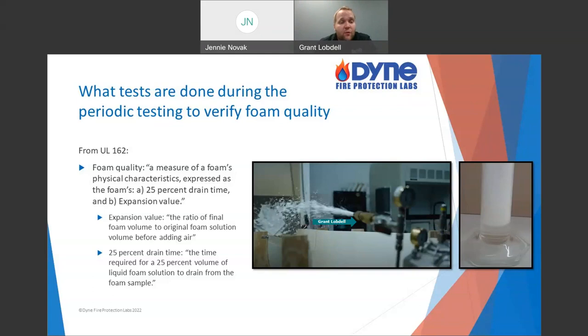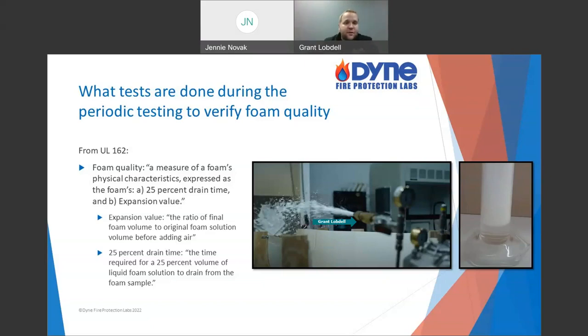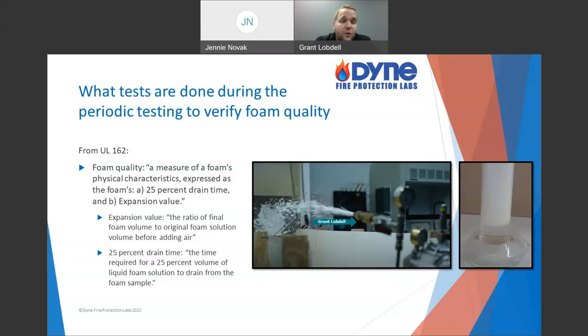Expansion ratio is very important with foam. We have Class B fires, liquid fires. If I were to just spray water on one, it's going to splash everywhere. Also, water is more dense than these Class B liquid fuels and gasolines — it's just going to settle on the bottom while the flammable fuel remains on top and stays on fire. So we need something that's going to be lighter than the fuel, sit on top of it and smother it. That's where foam comes in — we pull the solution full of air so it's less dense and can sit on top of the fuel hazard.